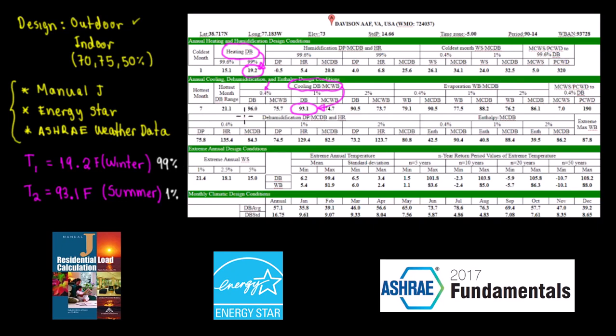Here's a trick to remember the 99th percentile and 1% — you always have to think 'above.' For the 99th percentile heating value, there is a 99% chance the temperature will go above that number. For the 1% summer value, there is only a 1% chance the temperature will go above that design temperature.